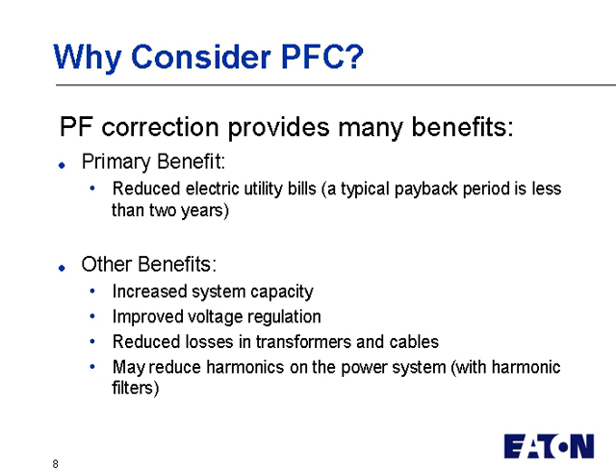Another issue that's important to people is voltage regulation, and capacitors help to improve voltage regulation. Another reason is you can reduce the losses in transformers and cables. Remember how I said if you reduce the overall kVA back through the system, you also reduce the current. So you're actually reducing I squared R losses back up through the system. And then finally, you can reduce harmonics in the power system if you use harmonic filters as a means to correct the power factor.